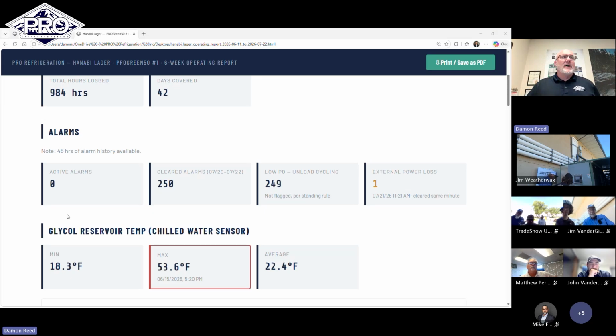That low PO, that's low suction pressure. That's actually an alarm that we use to cycle the compressor off under normal conditions. So it remains blue because it's a normal operating item that we utilize. But this one, the external power loss, popped up yesterday at about 11:20 a.m. Did we lose power or cycle power that you're aware of, Nick? No, I was not aware of that particular power outage.